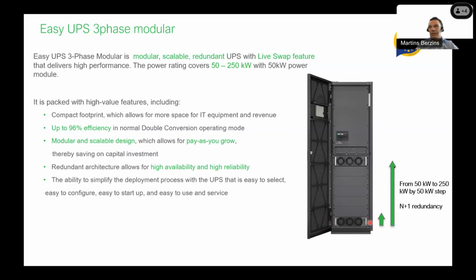And through modularity and scalability, by purchasing additional 50 kilowatt power modules, we can increase the power of the UPS up to 250 kilowatts. So in total we can add 6 50 kilowatt power modules inside this UPS, which gives us 250 kilowatts with N+1 redundancy. The UPS is very compact. The form factor of this UPS is an IT rack, 600 millimeters wide and 850 millimeters deep. The UPS can have up to 96% efficiency in double conversion online mode, which is a good standard for today's market. And of course, due to this modular architecture and scalability, it is a highly reliable UPS in terms of servicing and in terms of scalability options.